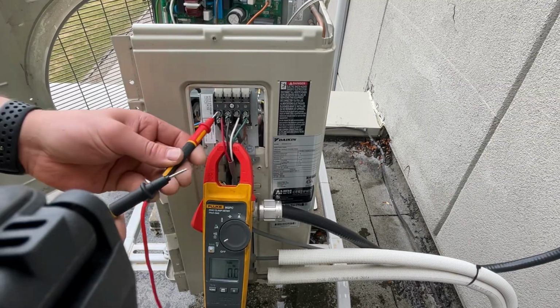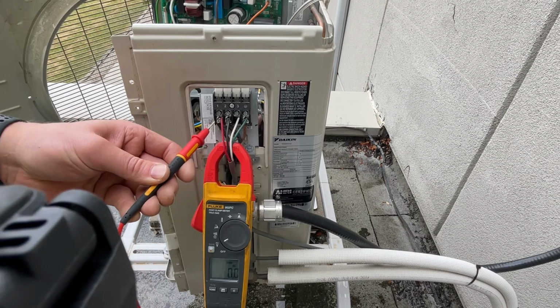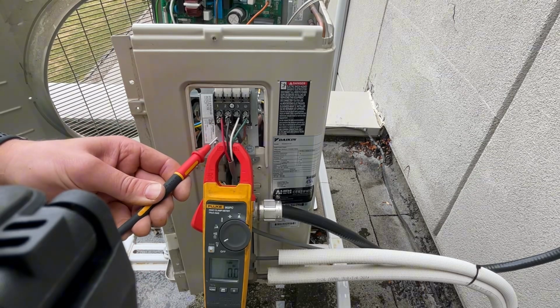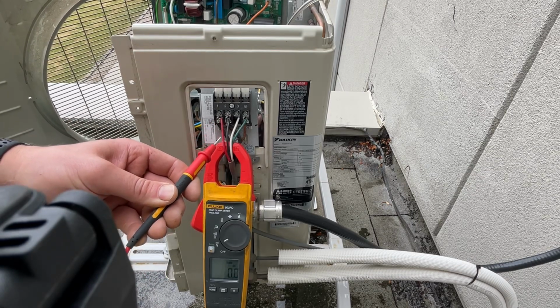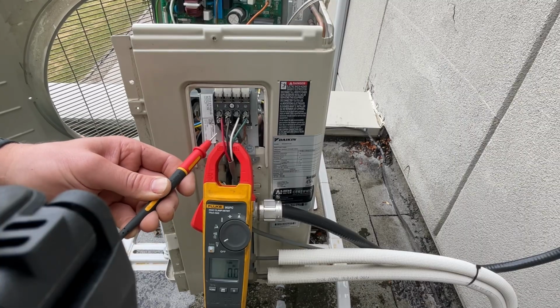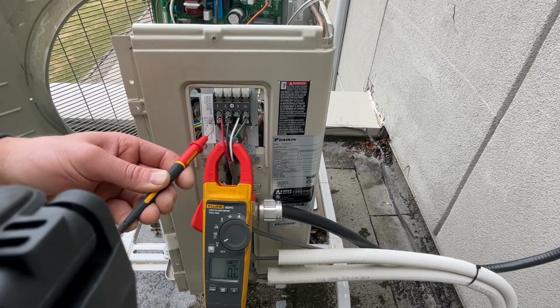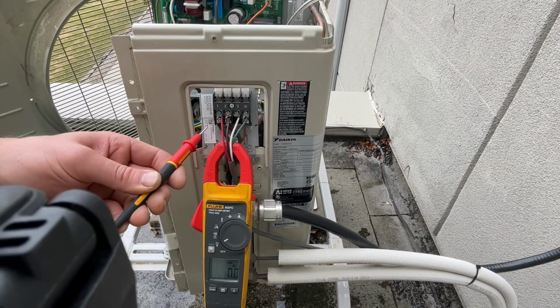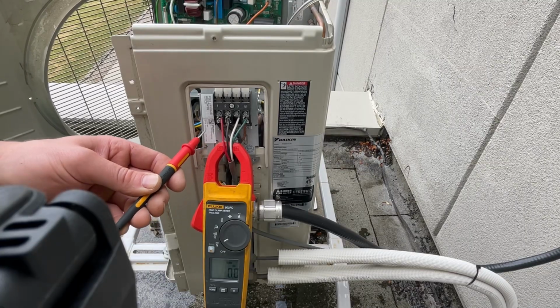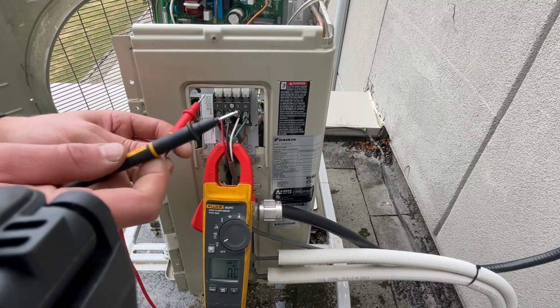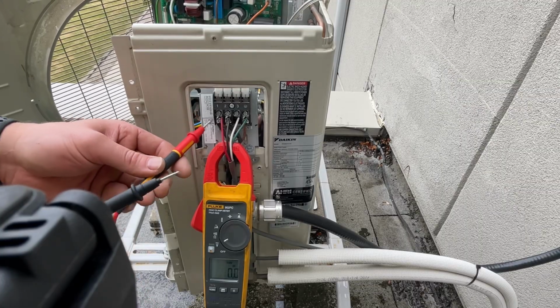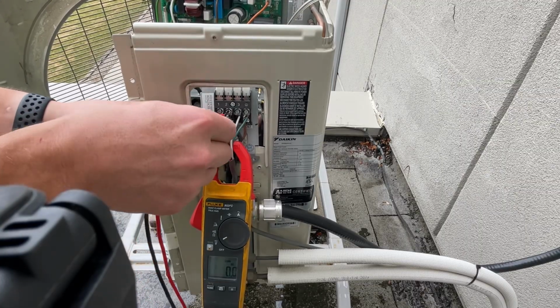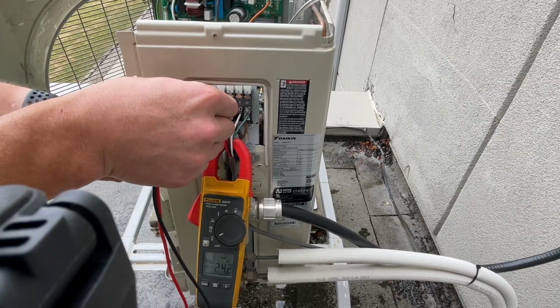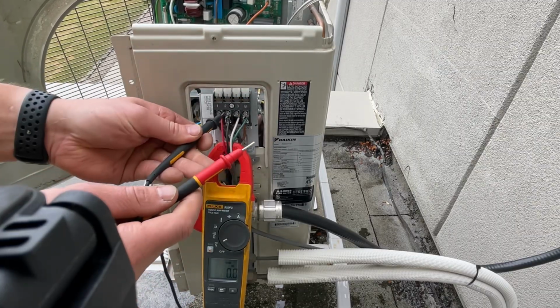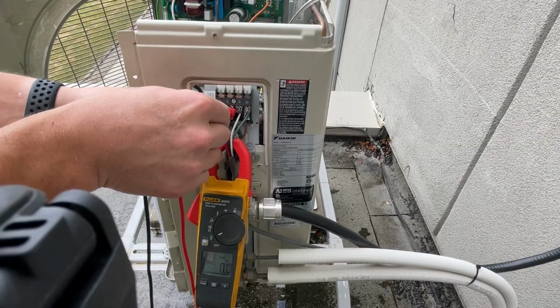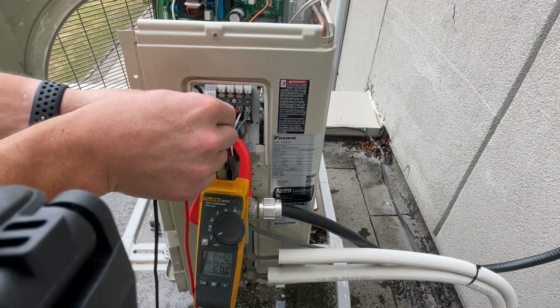So we're going to put these leads on, and what we should see is a pulsing range. So your voltage will start from 0 to 9 volts, then you'll go into teen volts, so 10 to 19, and then you're going to go up to double digits like 20s and then 30s. And keep in mind, you should never have a voltage above 45 volts DC. And you see my meter is going to pulse like crazy. And the only reason that says negative is because I have my leads backwards, but here we go. So watch this.